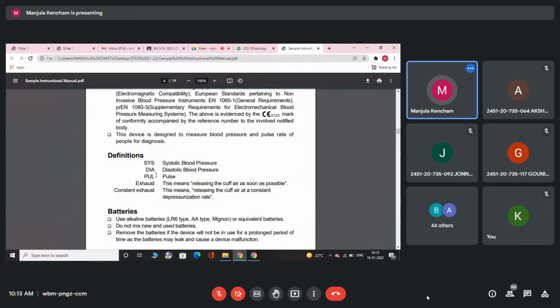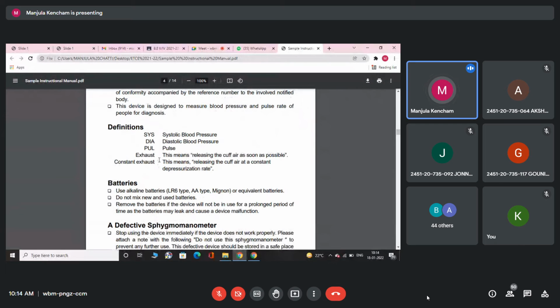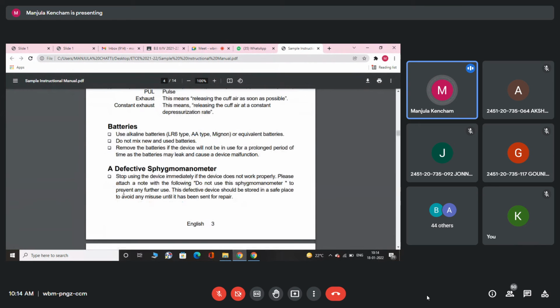Then definitions. They have used some abbreviations like sys, dia, pul, exhaust, constant exhaust, because the manual might show symbols that you can relate to. Batteries, because this is operated on insertion of batteries. What kind of batteries are we supposed to use? While using batteries, some people say maybe one is new, the other one can function, so they give the instructions very clearly. This is generally known, people overlook it, but when you are not using it, sometimes batteries get discharged. As a result, the liquid, the fluid flows out of it, so they say remove it from the instrument.